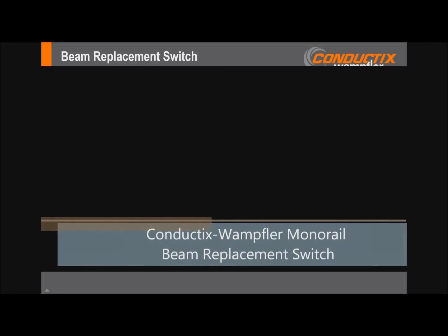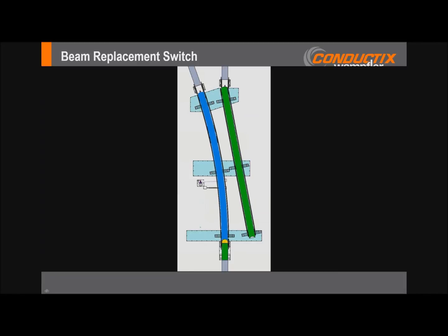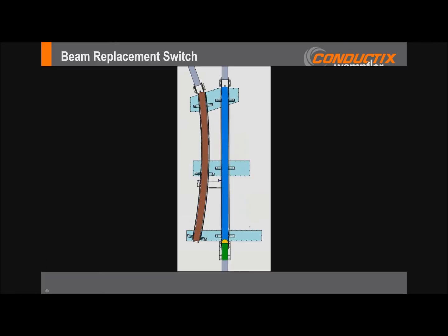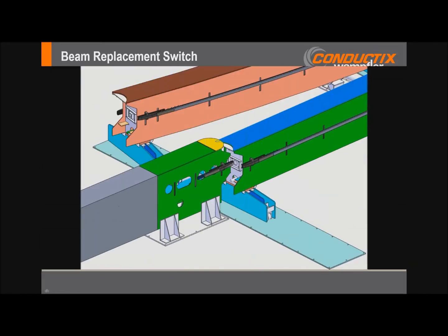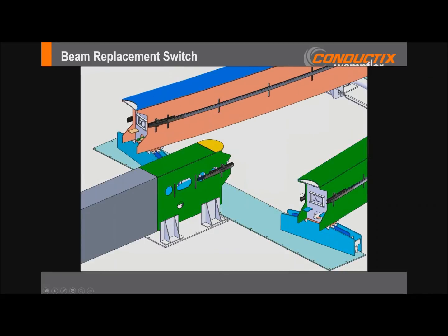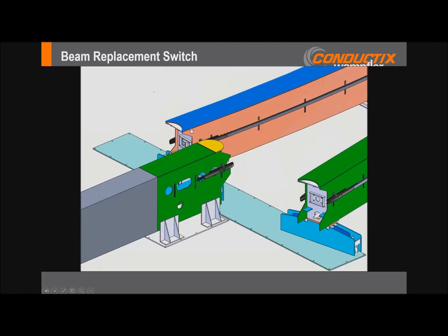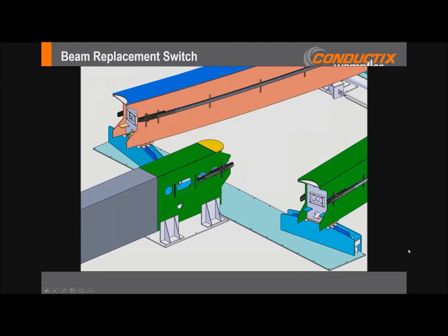I've got a little video here. I'll show you an animation of a sliding beam switch that we put together for our customers. We were figuring out how we were going to position these conductor bars to ensure clearances. So here you see the sliding beam and the conductors. This is a plan view. The conductors are on either side of the beams. It'll switch here to end view. So we're on the free end, and here you can see these conductor elements. Those conductor elements are passing fairly closely to the beams as well as to the opposing conductors.